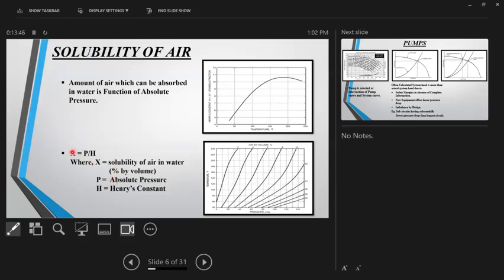So, absolute pressure in the system is maximum at what point? Obviously, at the lowest point. Correct. If it is a commercial building or a hotel, if the plant is in the basement, obviously the absolute pressure is basically operating pressure plus your atmospheric pressure. So pressure will be maximum at the lowest point. So at the lowest point, the solubility of air will be maximum.